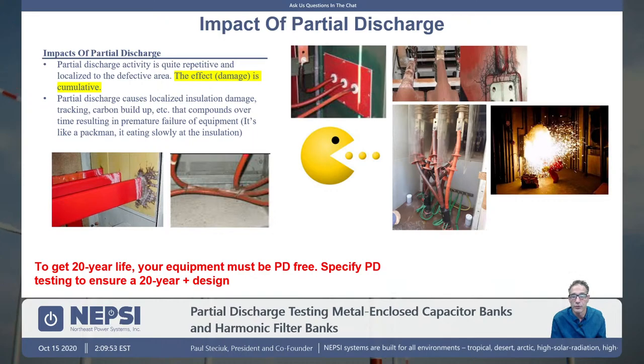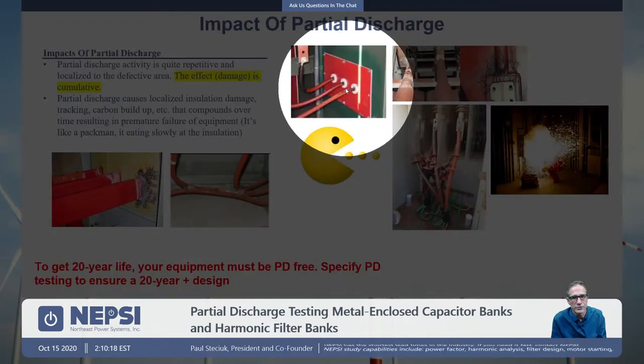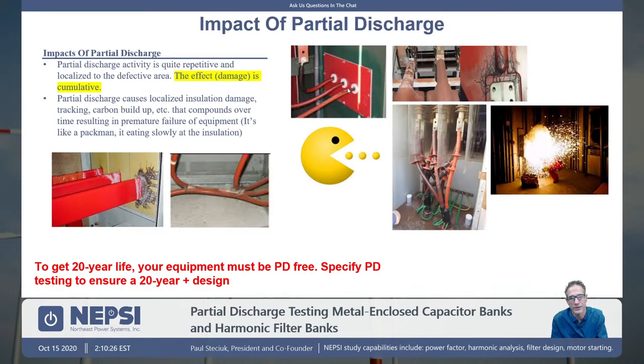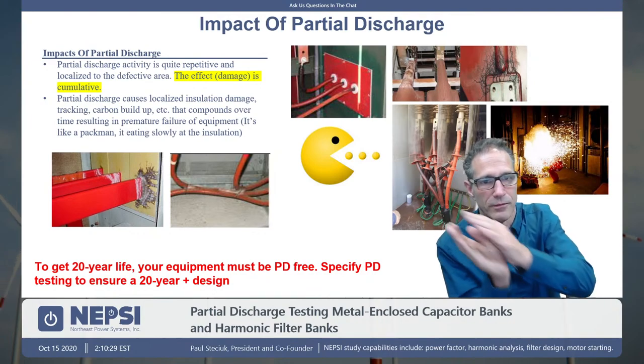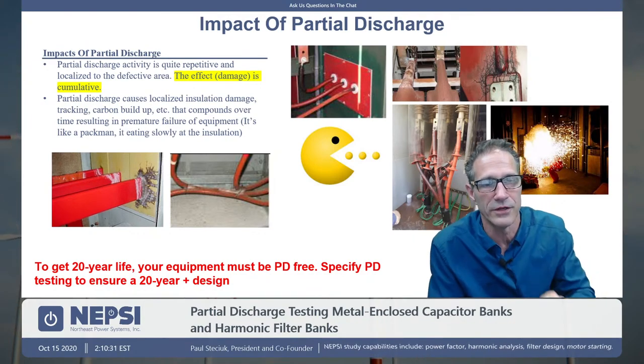So one thing to remember is whenever you see medium voltage jumper cable, it's never to be applied at ground potential. You're to post it off insulators to make sure that it doesn't have the electric field stress at the point where the cables are touching the ground. Another common place you see issues of partial discharge is pass-throughs here. You can see the carbon buildup along the cable here. And what's going on is the partial discharge is eating away at the insulation. I got that Pac-Man there to help you think about it. It's eating away at the insulation.